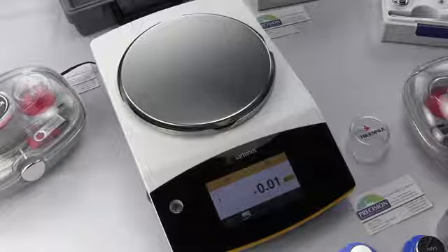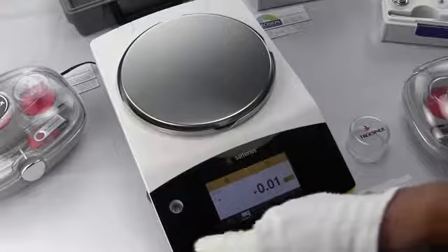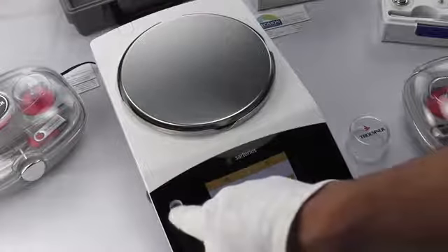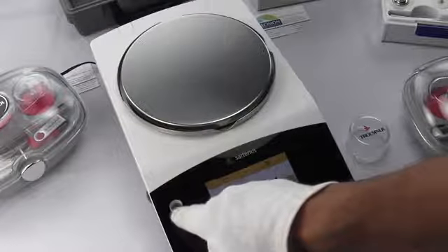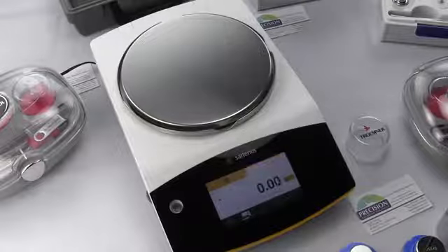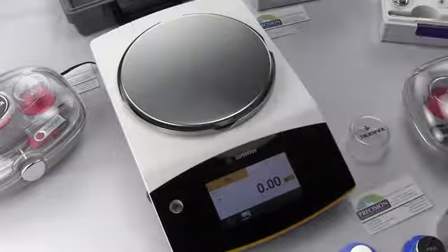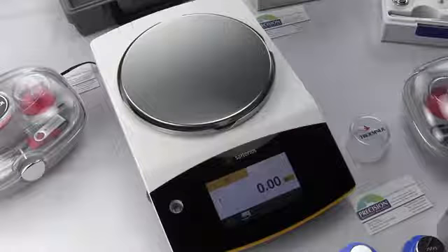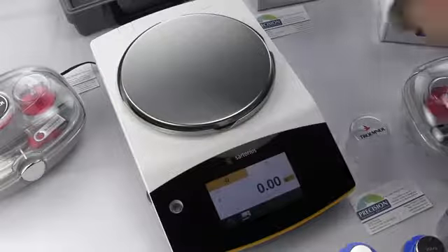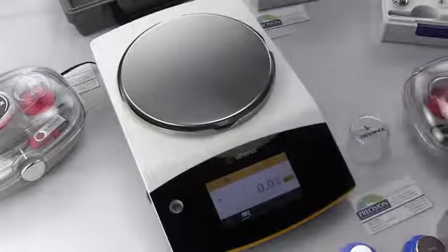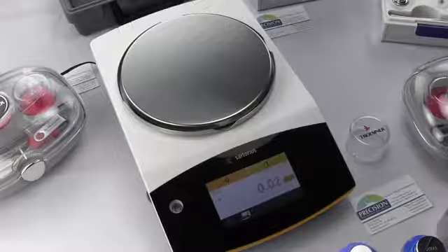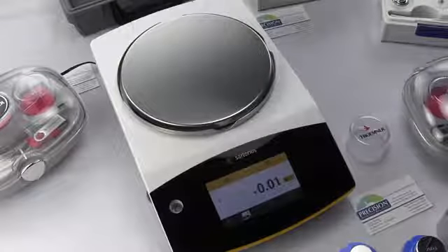The first thing you want to do is make sure your balance is level. We have a spirit level bubble here, and we have it right in the center. The next step, we want to make sure the pan has nothing on it. The pan is empty. We also need a stable environment with no air currents. If we had air currents, you can see what happens when I wave my hand. So we need a stable environment altogether.